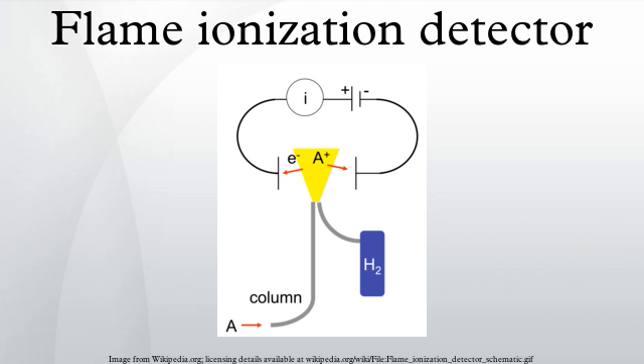The ions thus are attracted to the collector plate and upon hitting the plate, induce a current. This current is measured with a high impedance picoammeter and fed into an integrator.